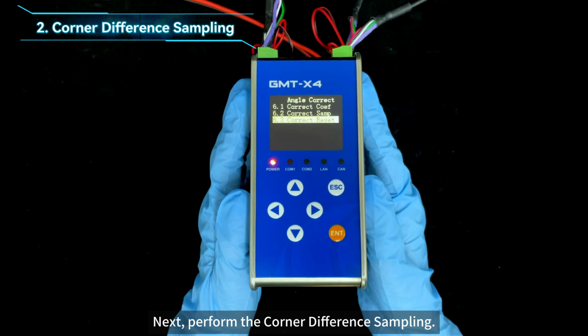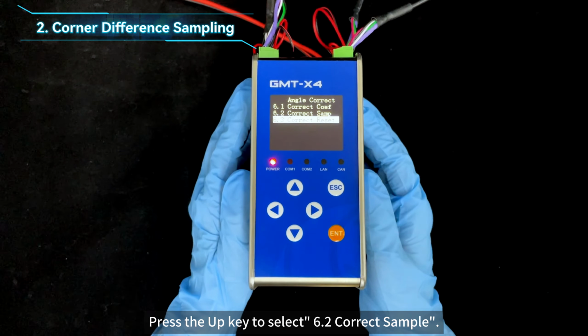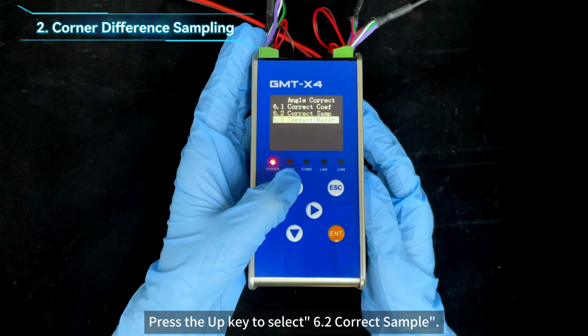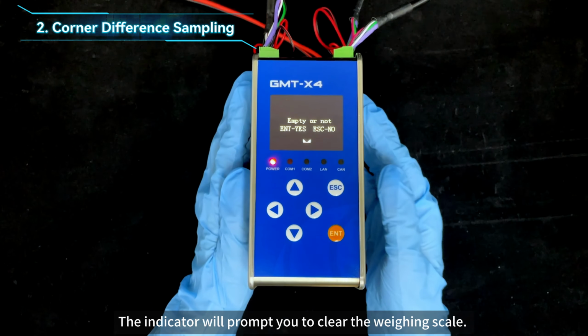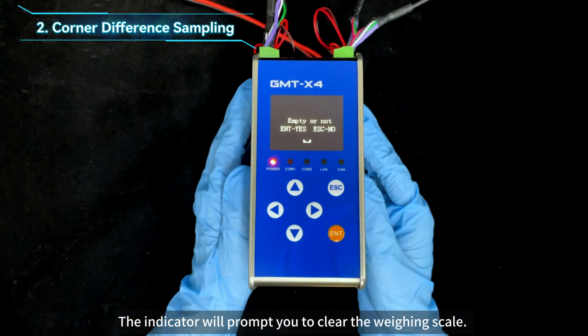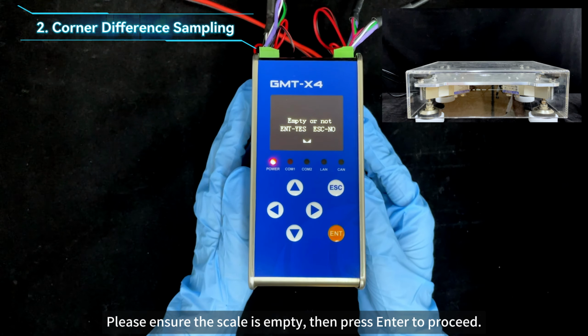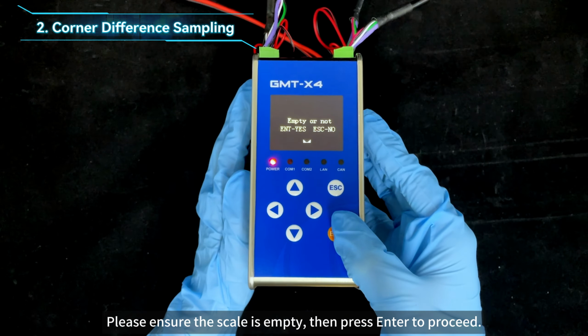Next, perform the corner difference sampling. Press the up key to select 6.2 correct sample. The indicator will prompt you to clear the weighing scale. Please ensure the scale is empty, then press Enter to proceed.